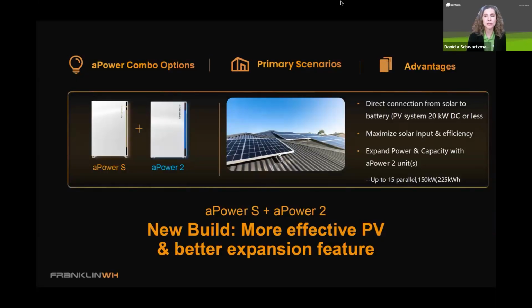Question 1: does the inverter shave solar production if solar input is over the 11.5 kilowatt inverter max? So there can be some clipping if you exceed 15 kilowatts of solar production inside the DC busing. For example, if you were producing 16 or 17 kW, you could see some clipping, either from the output capped at 11.5, which would derate the charge rate, or if you had minimal output, it would top off the charge rate. So there is some clipping after 15 kW. It does depend on how you're designing the system for aPower S. You don't want to max out the DC input if it's a fully south-facing array -- that's going to be better spread across maybe multiple aPower-Ss. However, if you got 20 kW across east and west facing, that real power output likely will not exceed that 15 kilowatts. So it just comes down to best practices in terms of design, but you won't see clipping until after 15 kW of PV production.